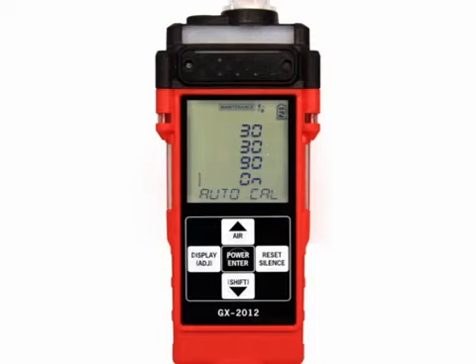With the cursor next to the AutoCal selection and AutoCal displayed along the bottom of the screen, press and release the Power Enter button. The value will begin to flash. Use the Air or Shift buttons to select on or off. Once a selection is made, press and release the Power Enter button to save it. The value will stop blinking. To exit the Bump Set menu, use the Shift button to scroll to Escape and press and release the Power Enter button.